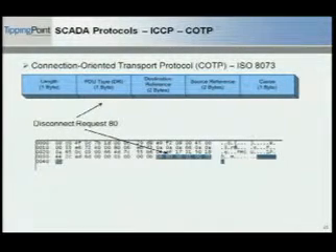So here's the other thing. If you are taking down an ICCP server, you might want to make sure the cause is set to a value which is not suspicious. The last byte in that one is 81, which means it's due to congestion on the other end that the server is going down right now. If it is 80, then it's a normal cause, so the server is going down because of a normal cause. These are all things that people need to look into, and not expose these kinds of details.